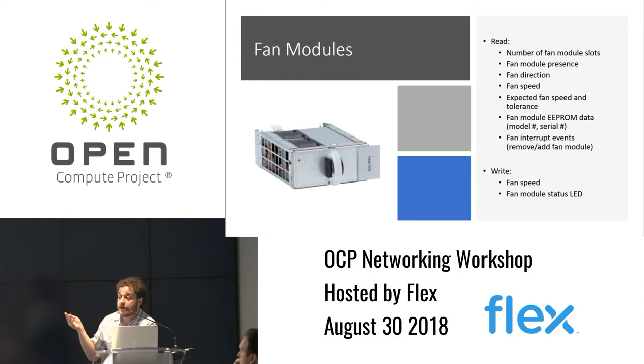We need to be able to get fan module EEPROM data. Again, each fan has a serial number, a model number burned into it. We need to be able to access that data. And we need to actually listen for fan interrupt events. Same with a PSU as well. If a PSU is removed, inserted, if a fan module is removed, inserted, we need to have that information available to us at the operating system, the user level of the operating system, so that we can make changes accordingly.